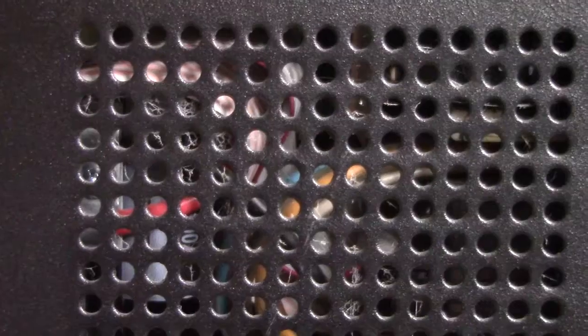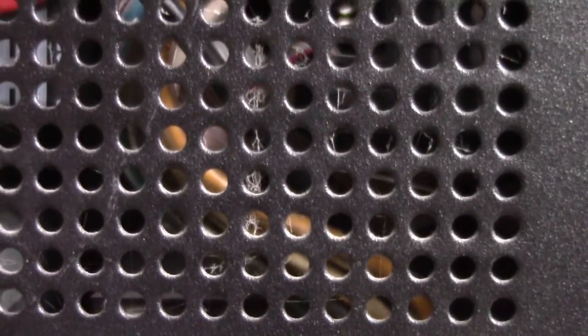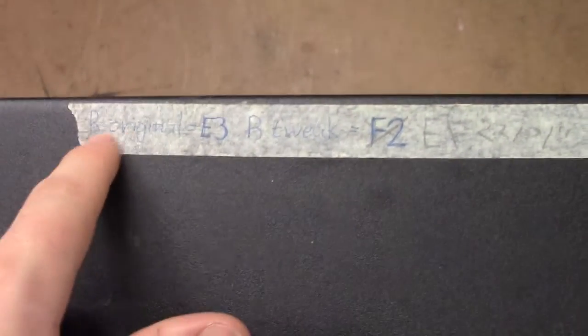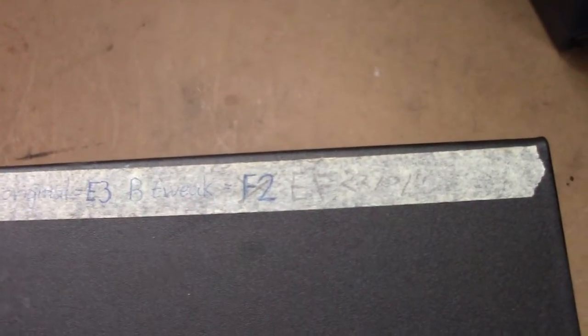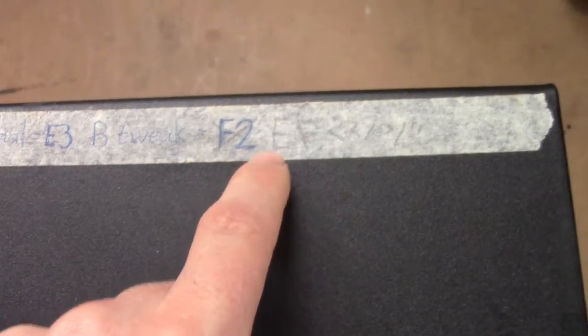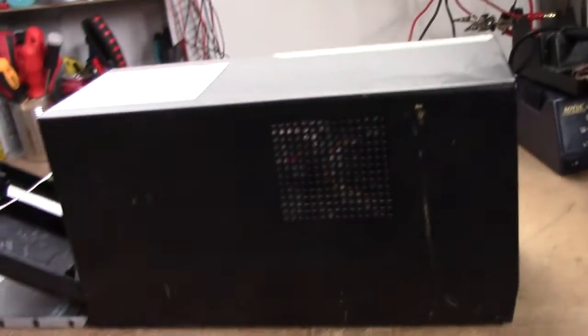Either way, time to get this one up on the bench. And the vent facing the wall, well, full of cobwebs, probably some mould in there as well, since this is in the basement. I noticed this thing has a sticker, or piece of tape, I put on it with the original battery constant and voltage constant, since I tweaked this back when I got it. This was one of the first Smart-UPSs I actually tweaked, which gives us a bit of history and certainly makes it a bit more deserving of service.